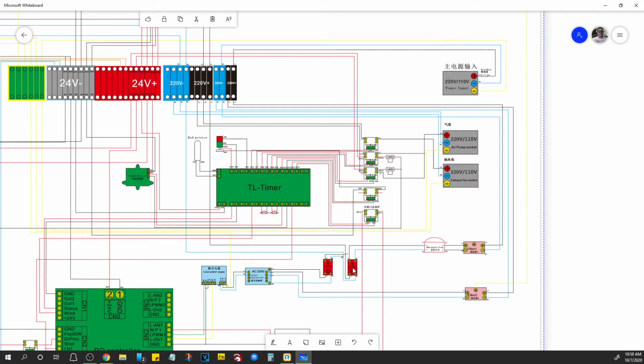Now, from the main power switch, that powers the contactor. I'm sorry, the contactor's on another one. The main power switch powers all of the rest of the power supplies, the low voltage stuff. It powers the 24 volt power supply, the 36 volt power supply, and some other things in there, contactors and such, relays. So then you have your laser power switch. Now what this does, it energizes this big contactor in there. That's that loud thunk you hear when you turn that laser power switch on and off. And that goes to the laser power supply only. It has its own separate dedicated AC circuit going through this separate filter, so it's isolated from the workings of the machine so you don't get noise on that line.